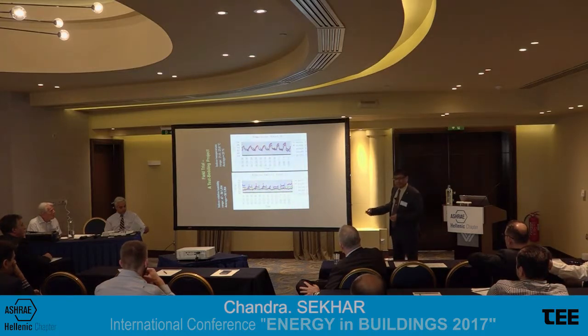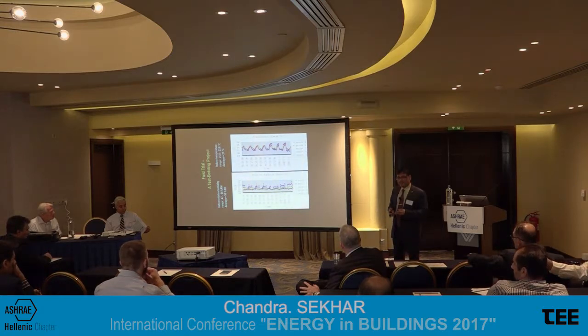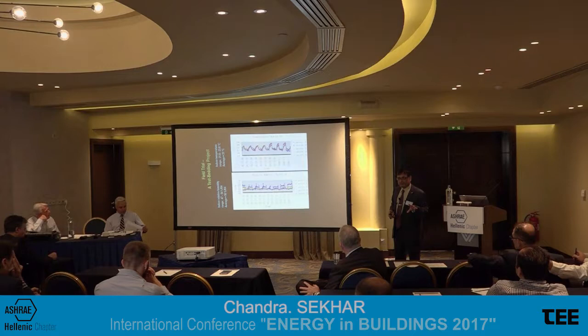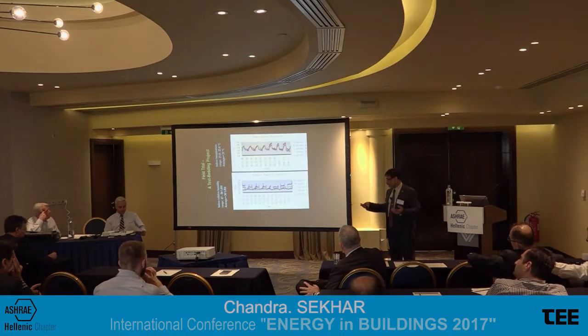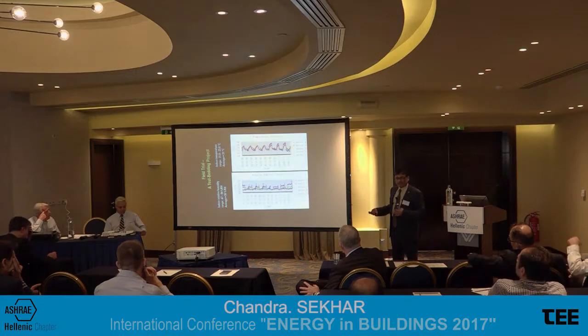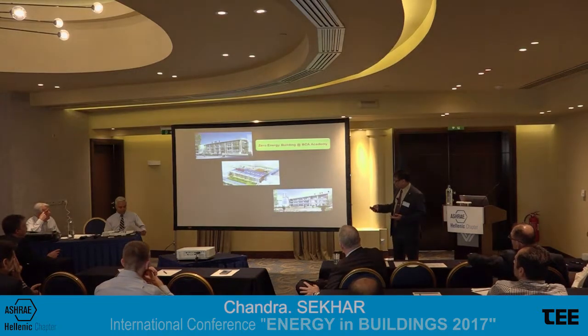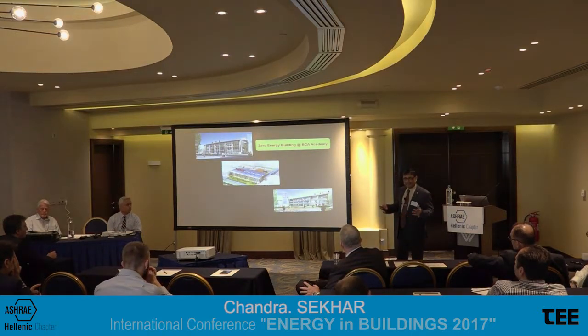And we had good positive feedback from the facilities manager, looking after this as part of a university facilities division. They noticed that the return air coming into the air handling unit was always considerably drier in terms of the RH level compared to their experience in other building AHUs. It just meant that the overall humidity control in this AHU and in this space was that much better compared to other conventional designs. That was 2005. The system is still running. The building is still in operation. We have almost always had positive feedback on the building.